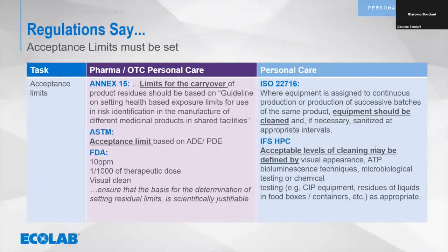The international featured standard then says you should define acceptable levels that cleaning should go to. That could be the visual appearance, meaning after cleaning, the visual acceptance criteria is there to show you that visual clean is what is required. And maybe also a kind of microbiology on a surface - ATP measurements, bioluminescence techniques could be used to identify if you have cleaned down to a proper level.